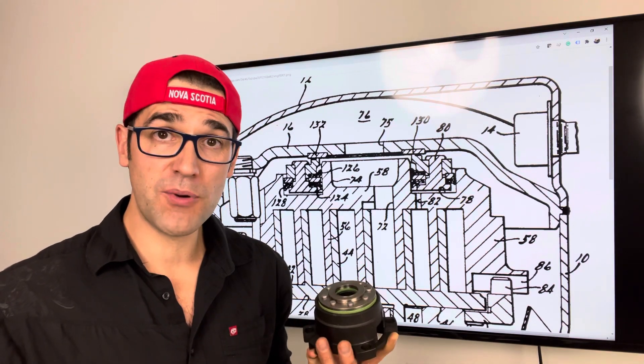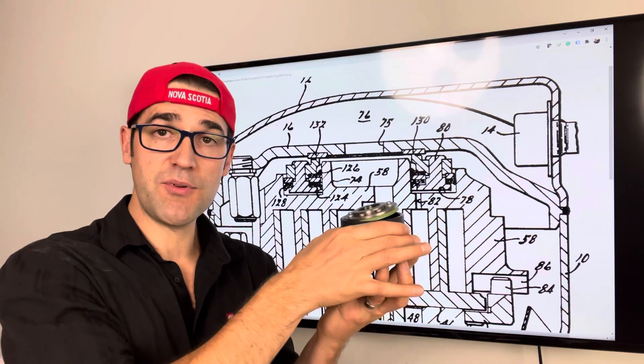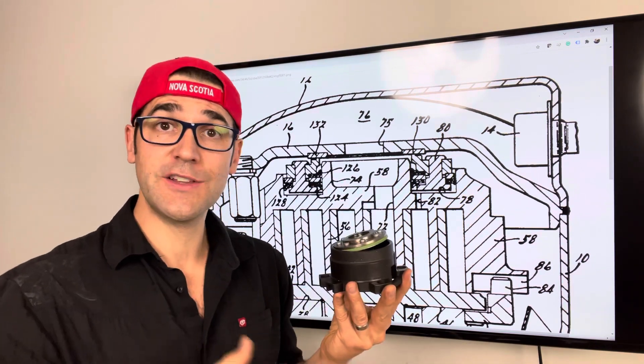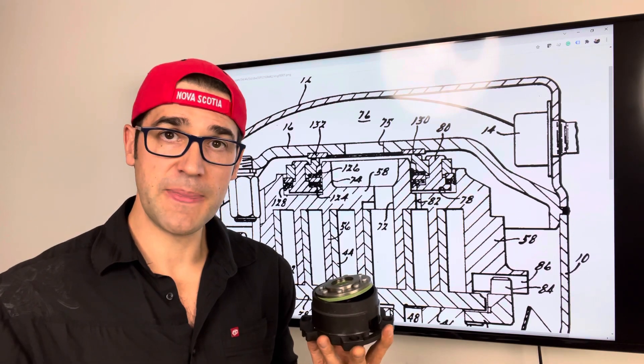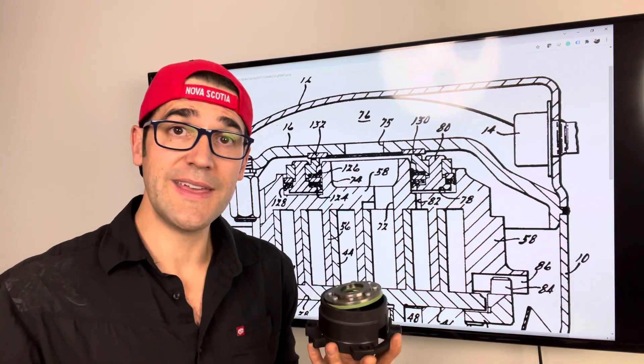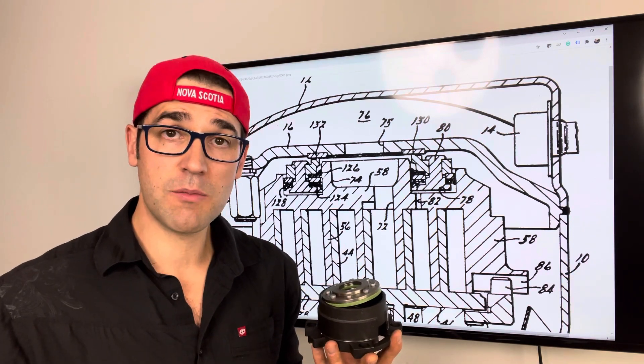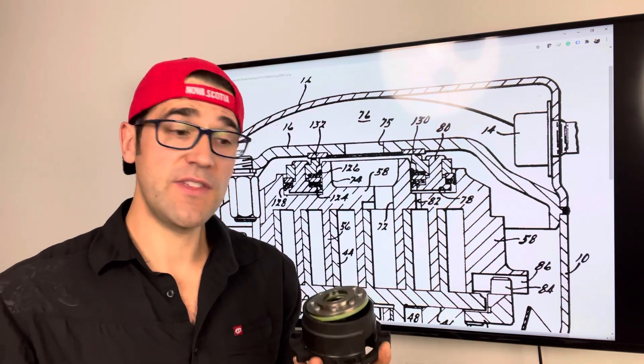If you have too high compression ratio, this unbalances and separates the scrolls. The compressor will continue to run until it trips off on its internal overload and then it'll shut down. You want to be aware that the compression ratio was too high - 11 to 1 on air conditioning compressors, 26 to 1 on refrigeration compressors. If it gets over that it unseats, separates the scroll and it trips off.